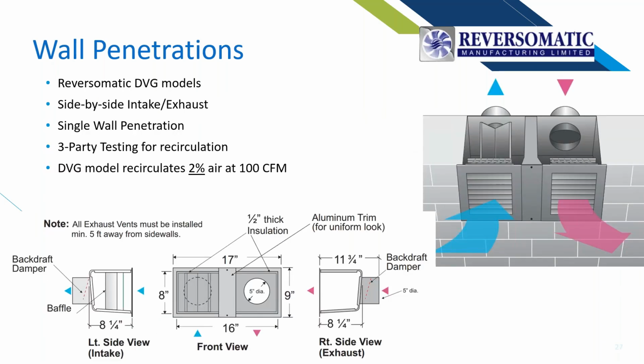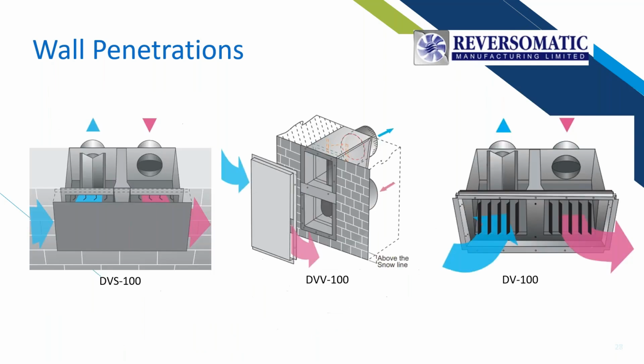So this is what it looks like. This is the DVG model. In this model specifically, we only recirculate 2% of air at 100 CFM. And by the way, we have third-party testing to back that up. There are some really great details about this, but there are a few different options too. So if your architect is sold on a specific look, we can do that. If they want a vertical look, we can do that.